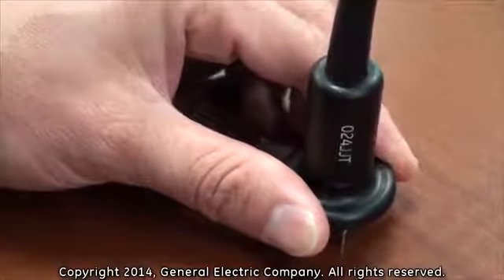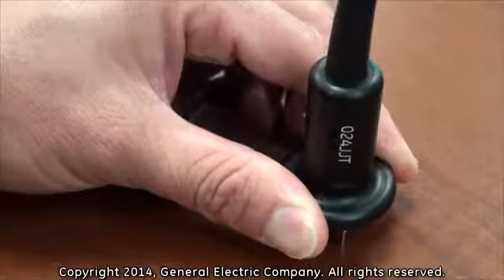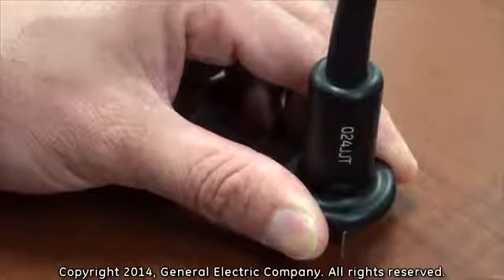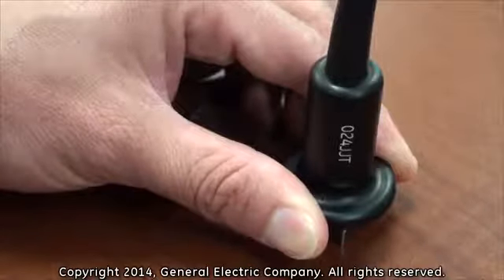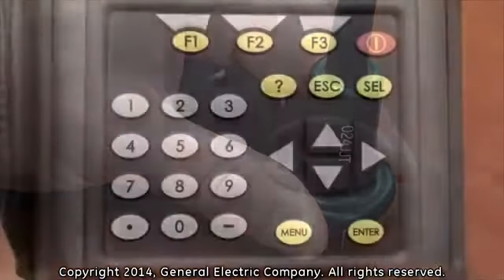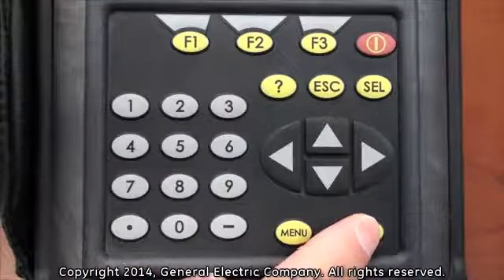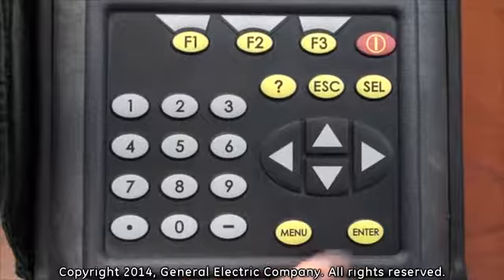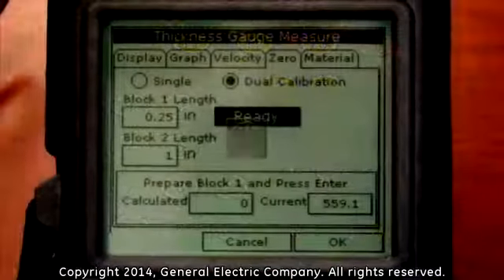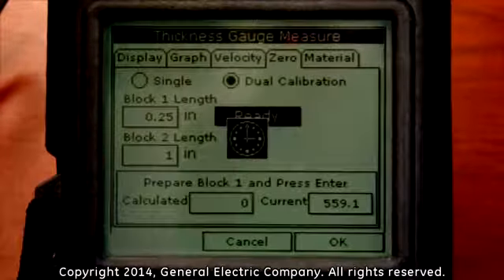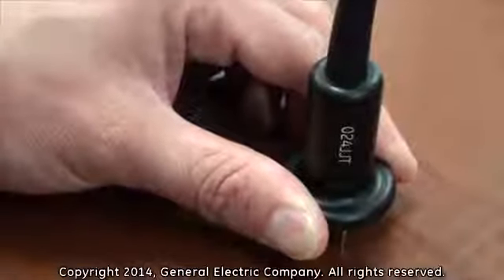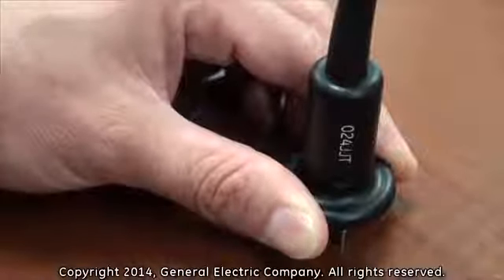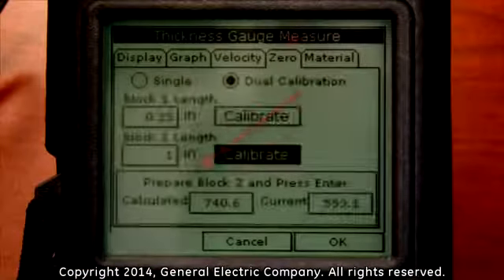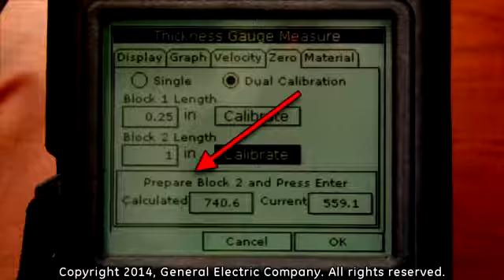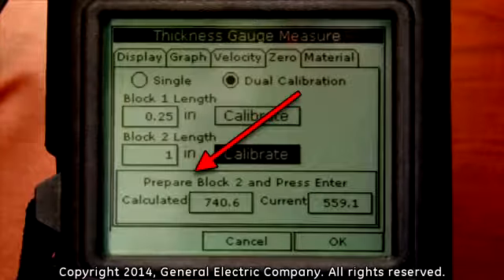Do not apply too much pressure while pressing the thickness gauge to the test block. This will ensure a more accurate calibration. With the thickness gauge firmly pressed to the test block, press the Enter button on the keypad to calibrate. Hold the thickness gauge steady and try not to move it while the calibration is being performed. After a few seconds, you will see that the calibration is accepted and the display at the bottom now requests you to prepare block 2.